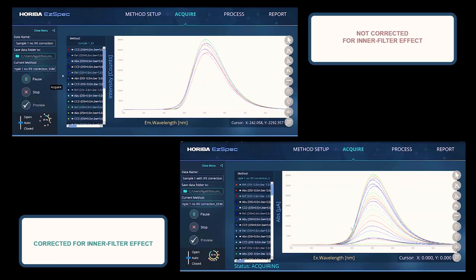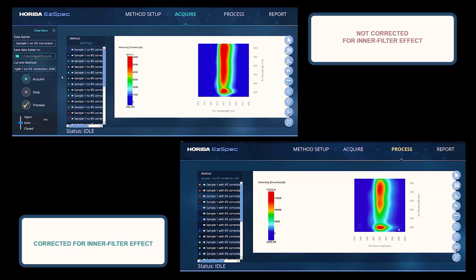And in one application in particular, where we look at excitation emission matrices, we're really taking full advantage of absorbance and transmission along with EEMs. Having this two-in-one capability allows us to correct for the inner filter effect, a well-known physical phenomena. And that allows us to really get a very true molecular fingerprint.